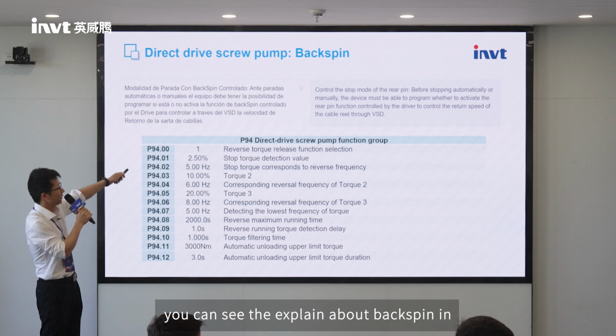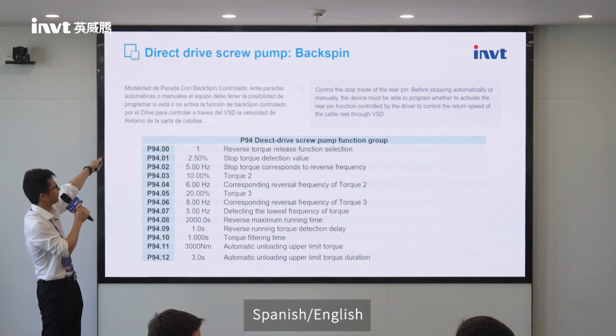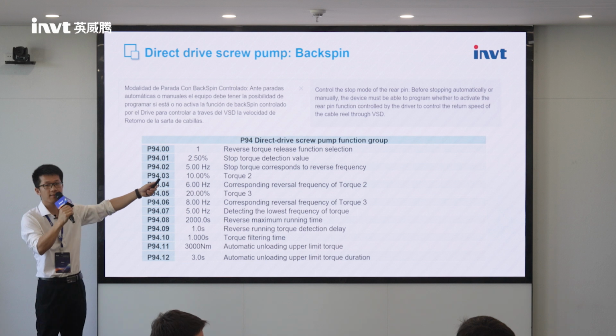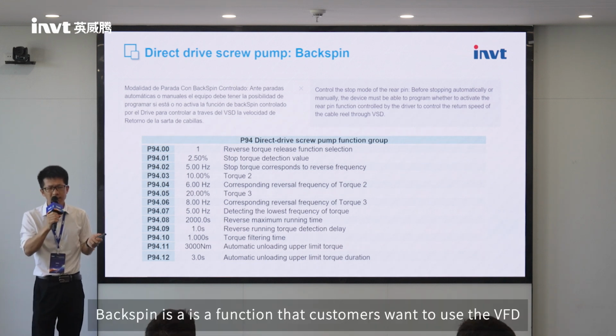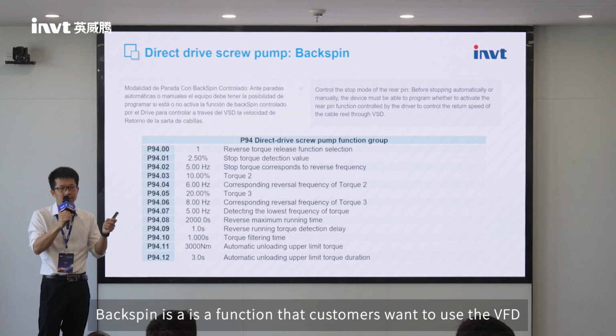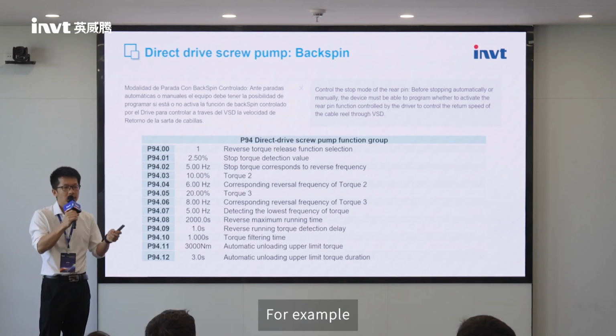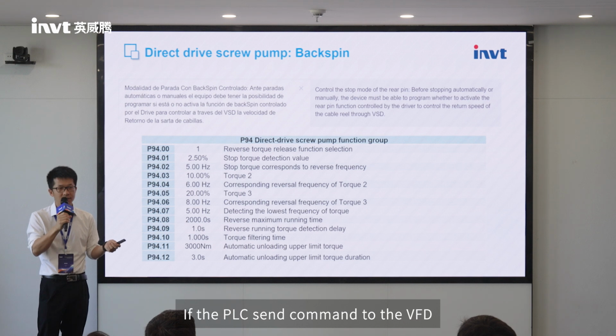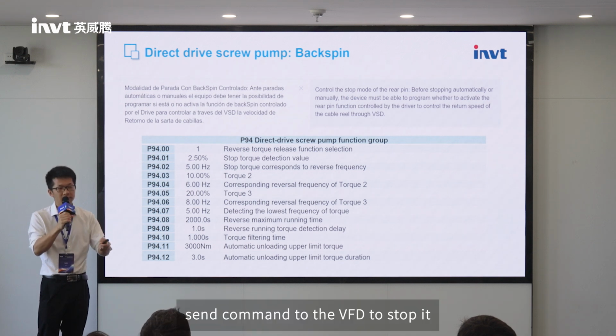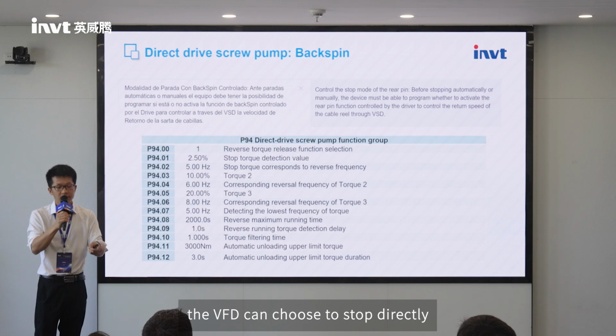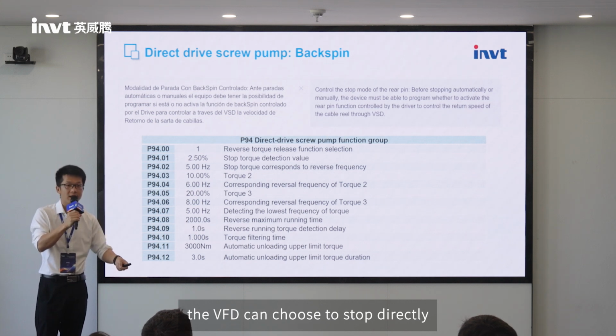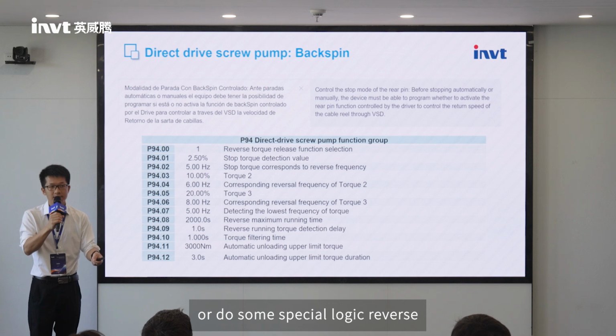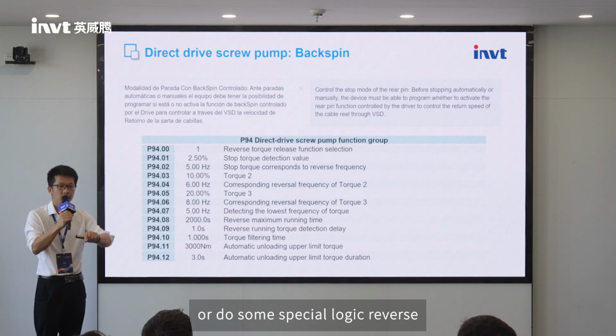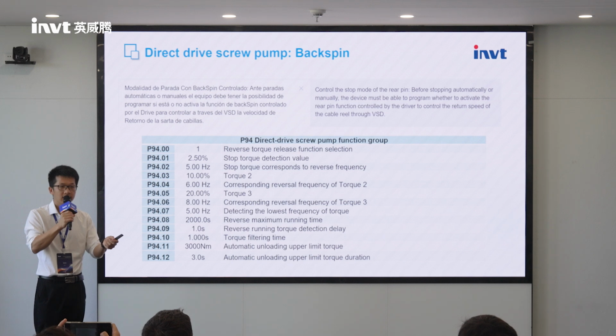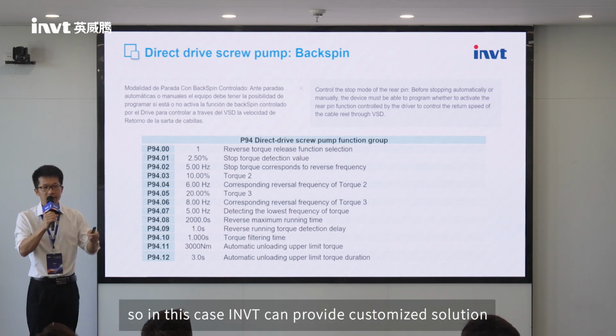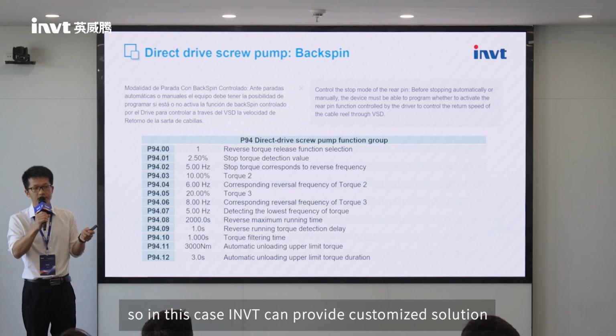Backspin is a function customers want to use in the VFD. For example, if the PLC sends a command to the VFD to stop, the VFD can choose to stop directly or perform some special logic, like reverse running. In this case, INVT can provide a customized solution.